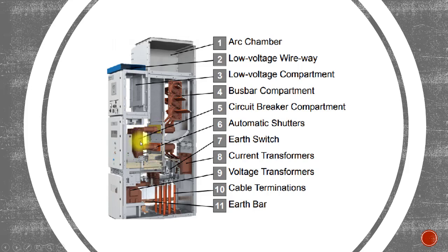The moving parts of the circuit breaker are inside the circuit breaker trolley. Number six is the automatic shutter. As soon as the breaker is racked out, the shutter closes, preventing anyone from touching the busbar or cable side. This is a safety requirement. In good designs, the shutter is also provided with a padlock.